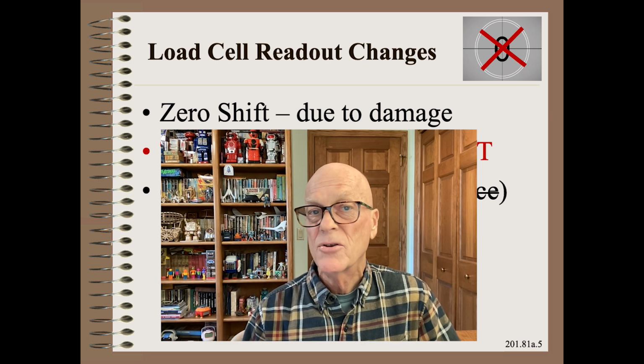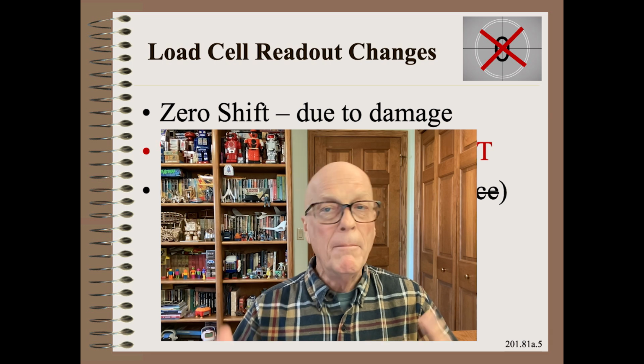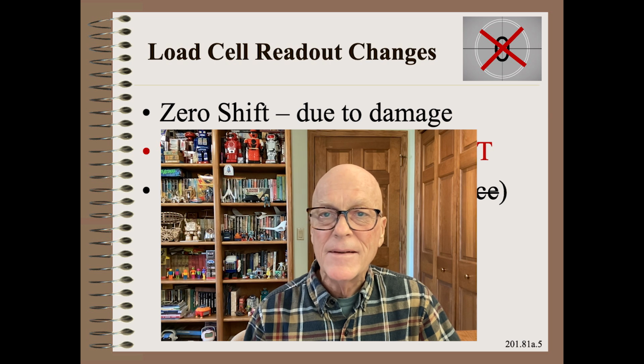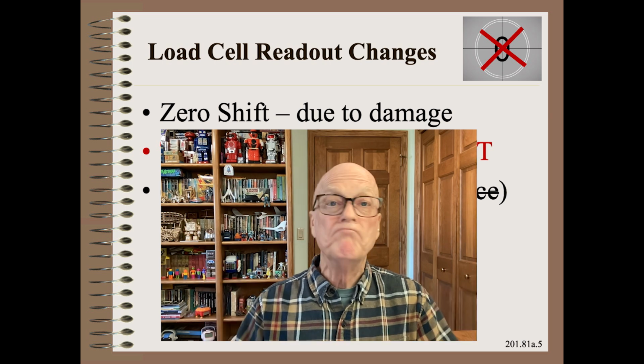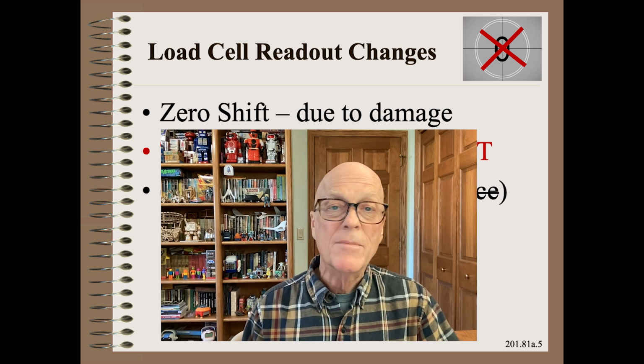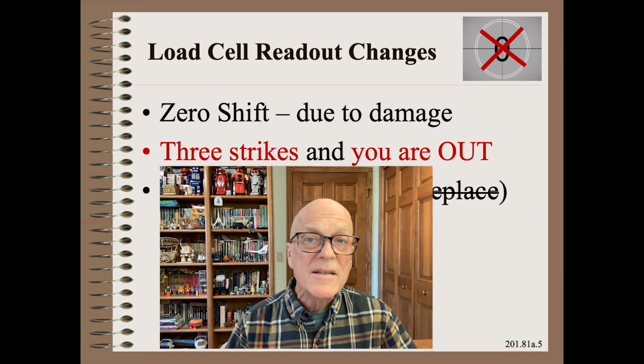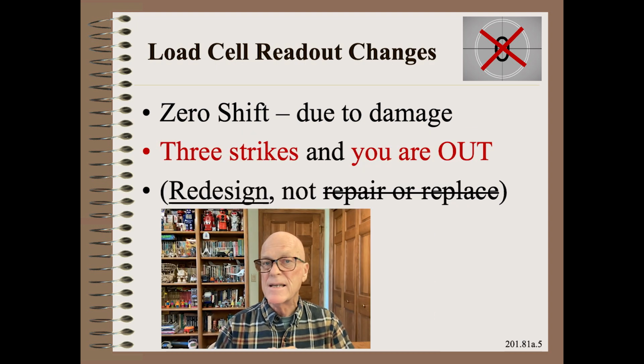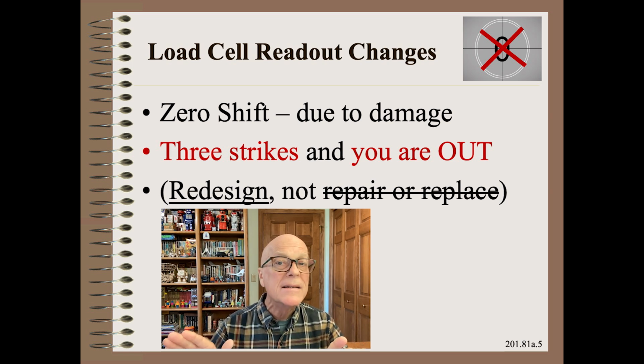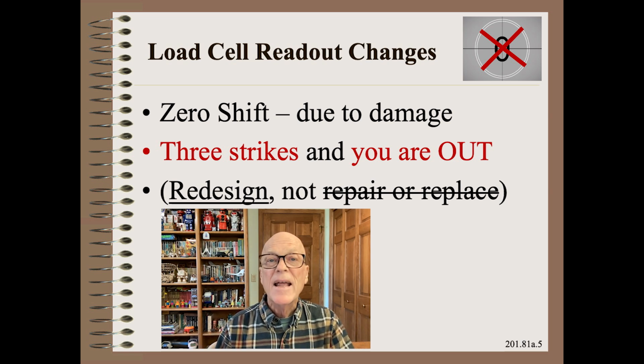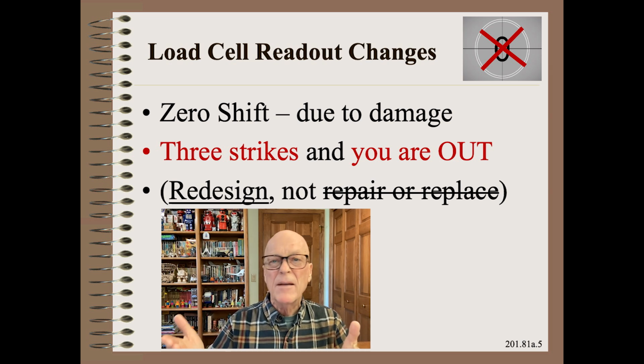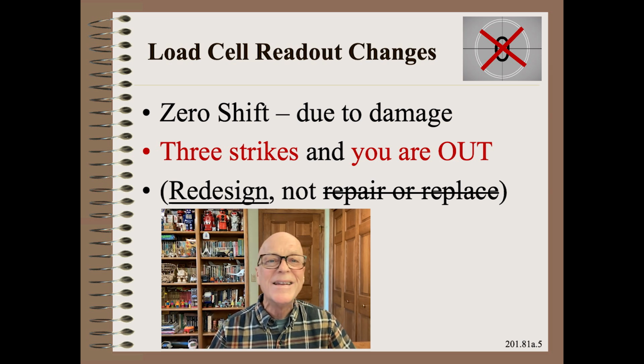Moving on. So the first time the operators see a zero shift, they should call maintenance. Maintenance responds by re-zeroing and possibly calibrating gain. If you see one failure, a second should not be surprising. Maintenance again responds by re-zeroing. However, the third time this happens, the proper response is not to repair or replace, but rather redesign. That is because the load cell or amplifier is not trustworthy in this application.